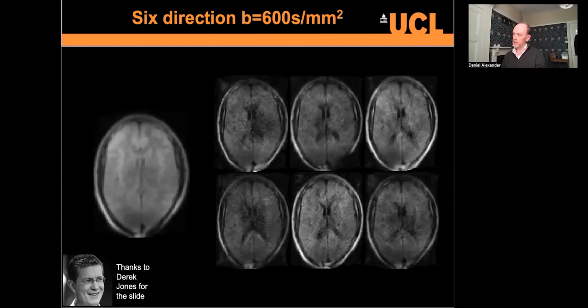Well, just to give you a taste, part of the problem is that each single diffusion weighted image on a hyperfine system requires about 10 minutes of acquisition time. And the absolute minimum you need to do tractography is 7 of those images. So right there, there's an hour and 10 minutes minimum of acquisition time in order to even have a hope of doing diffusion tensor imaging, and that is just not feasible on kids. So what we're thinking about is ways of possibly speeding that up.